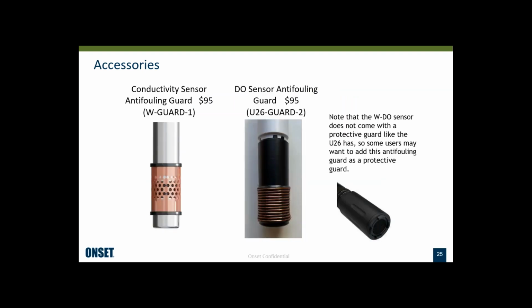So here's the anti-fouling guards. For the conductivity sensor, it's basically a sheet of copper. It's got many holes punched in it, and it wraps all the way around the conductivity sensor. It's held in place by 2 O-rings, which hold it securely in place. But it also makes it easy. You just slide off the O-ring and the copper guard for cleaning the sensor as needed. So it's easy to do that servicing as well.